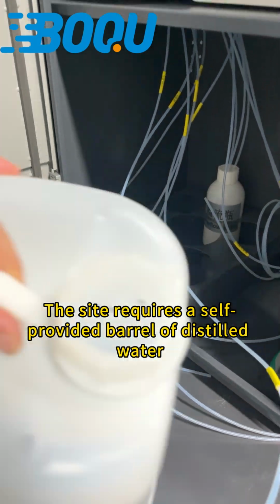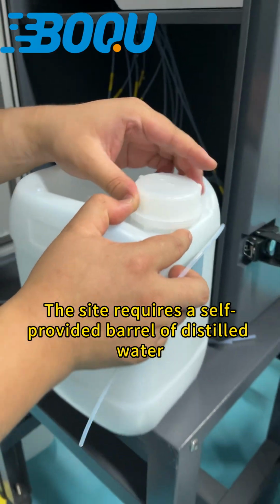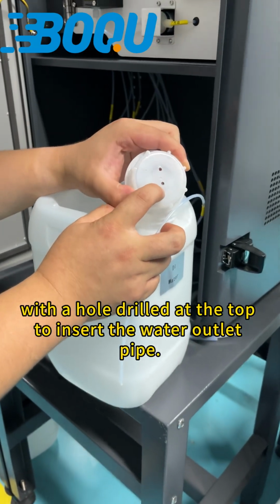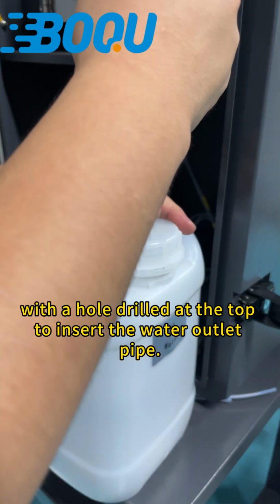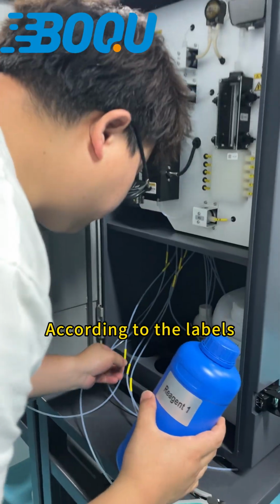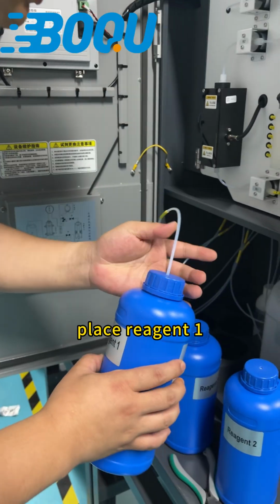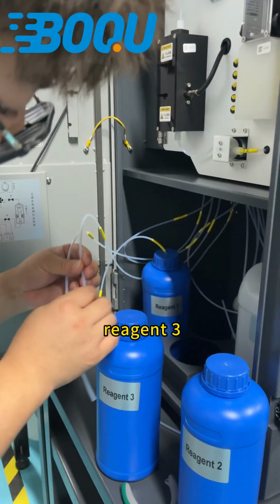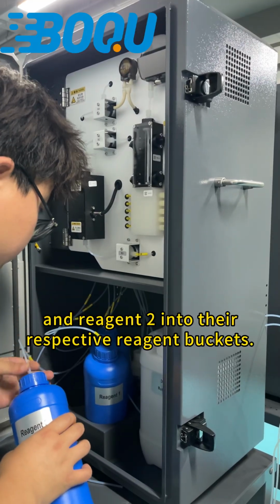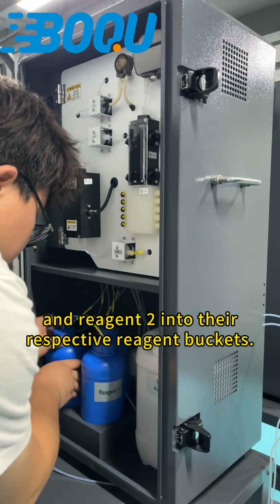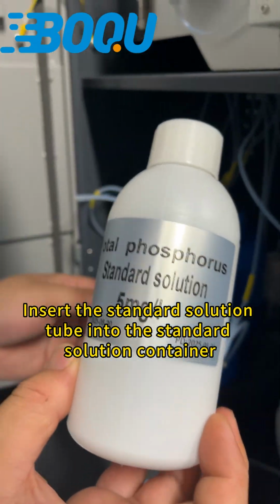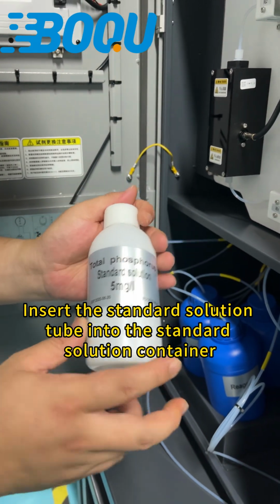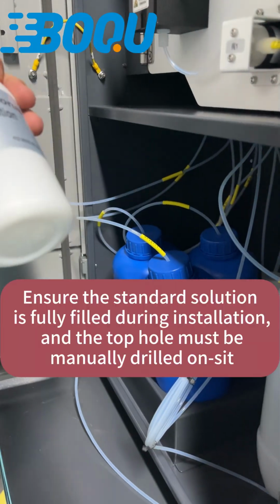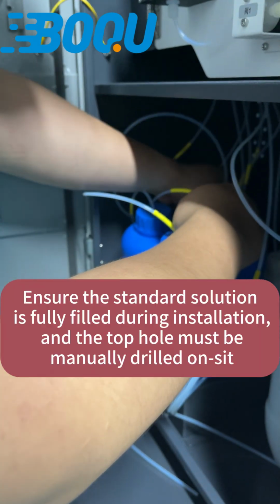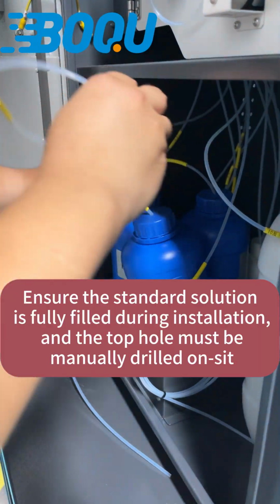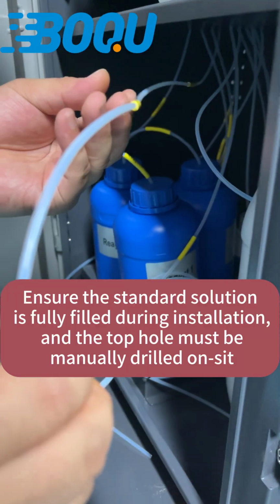The site requires a self-provided barrel of distilled water, with a hole drilled at the top to insert the water outlet pipe. According to the labels, place reagent 1, reagent 3, and reagent 2 into their respective reagent buckets. Insert the standard solution tube into the standard solution container. Ensure the standard solution is fully filled during installation and the top hole must be manually drilled on site.